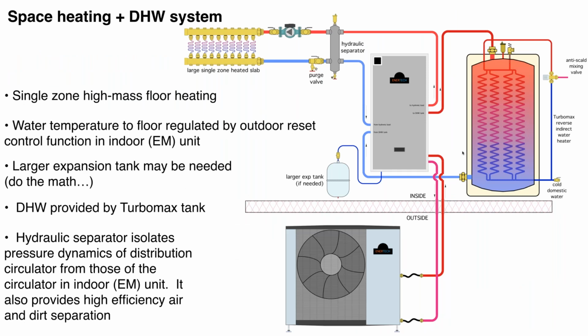Again, we're back to that standard setup right here, space heating plus domestic water. As I mentioned, most residential applications, and really this unit was designed primarily around that concept, are going to have the need for domestic water in sufficient quantities that it makes sense to heat that water with the heat pump. And certainly keep in mind, domestic water heating is an annual load. It's present 12 months out of the year, whereas obviously space heating is in the winter.